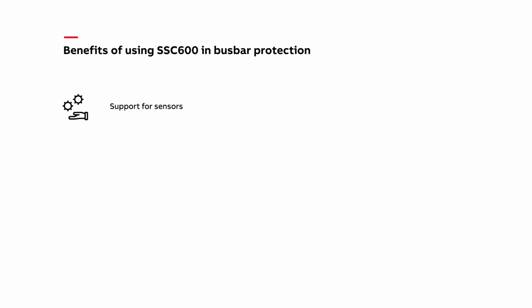Benefits of using SSC600 in busbar protection. The benefits of using SSC600 in medium voltage switchgear for low impedance busbar differential protection 87B include: SSC600 offers a sensor-based 87B protection solution, which is unique on the market. Current sensors have the benefit that they do not saturate, like conventional CTs. You also don't need another set of CTs, so the switchgear panel becomes smaller and lighter. The amount of wiring is reduced compared to a standalone 87B system.